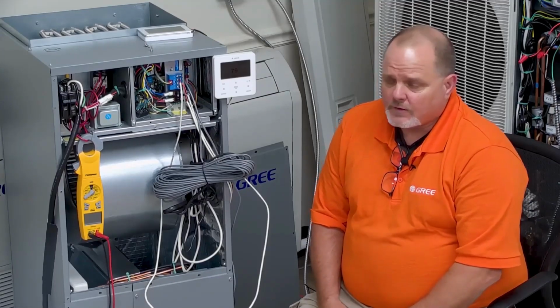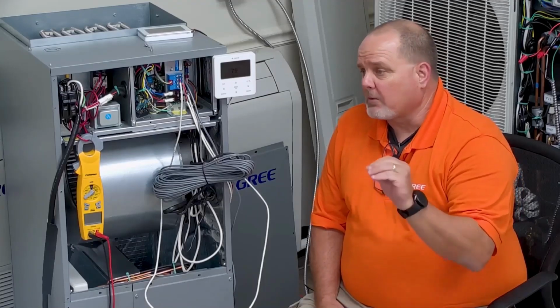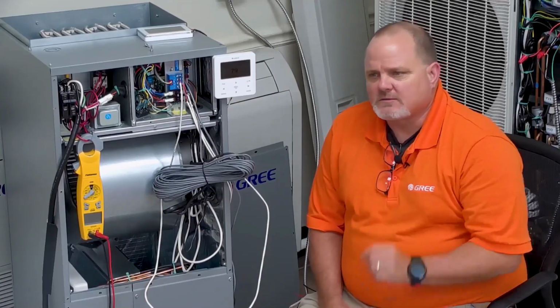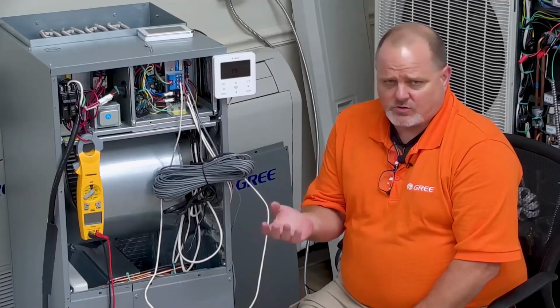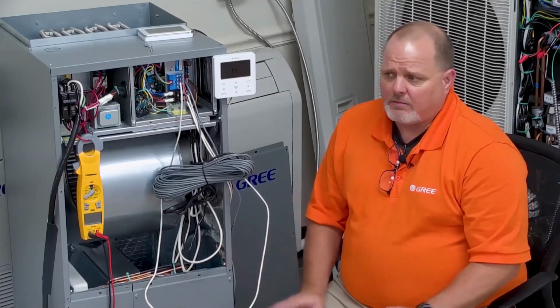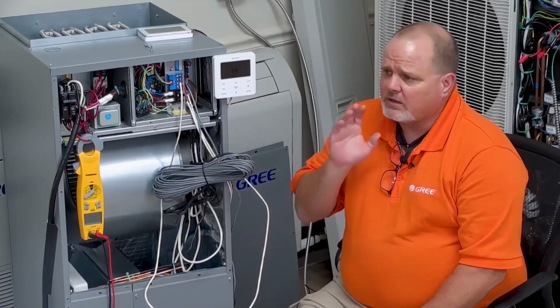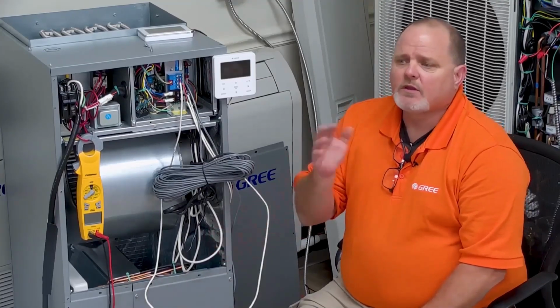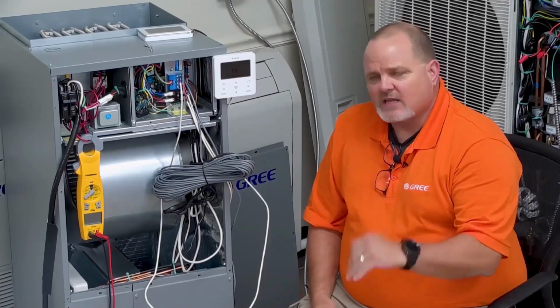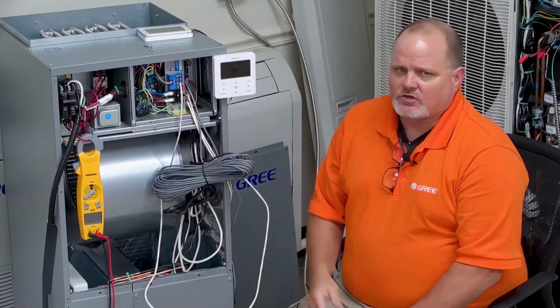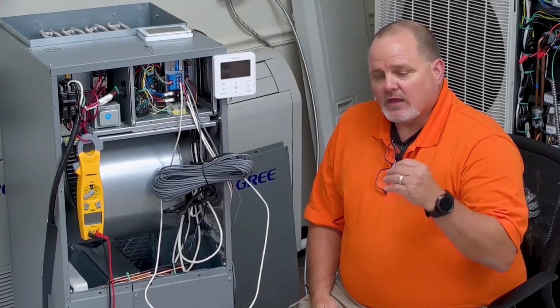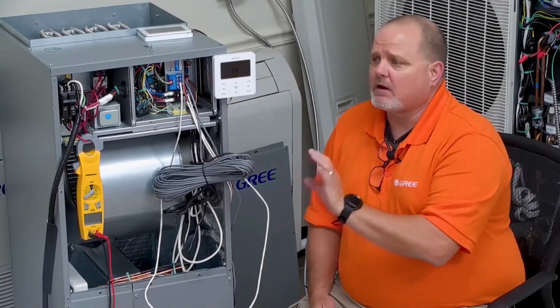You will now have your heat function, just like you did before with the other GREE controllers with the MultiPRO heat pump, but you're also going to have an emergency heat function, and you're also going to have an auxiliary heat function. So I'd like to talk a little bit about that first, because it seems like there's a lot of confusion in the industry between what emergency heat is and what auxiliary heat is. Emergency heat is exactly that, and meaning if the heat pump is dysfunctional for whatever reason, whether it's a MultiPRO heat pump or any other heat pump, if that thing's out on error code, can't defrost properly, whatever the case may be, the emergency heat function gives us the ability to set it to emergency heat, or GREE likes to call it E-heat function. By putting it in E-heat function, then the heat pump no longer functions until that gets serviced and repaired and fixed.